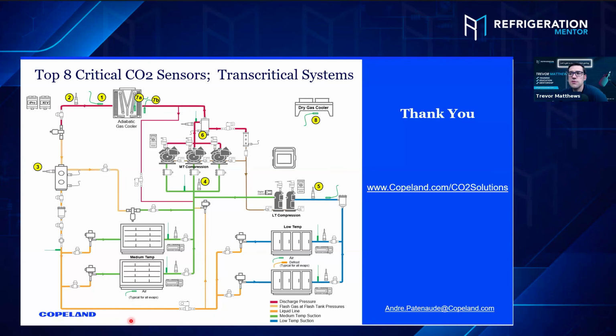Another one here is the T2 sensor. How far away from that T should it be? When you're doing that bypass, is there a recommendation? Should it be 6 inches? And that one should be insulated as well, right? 100% that needs to be insulated. There's no exact recommendation on the distance, but I would say 6 to 12 inches, but insulated for sure, because you've just got an average temperature coming from both ends.